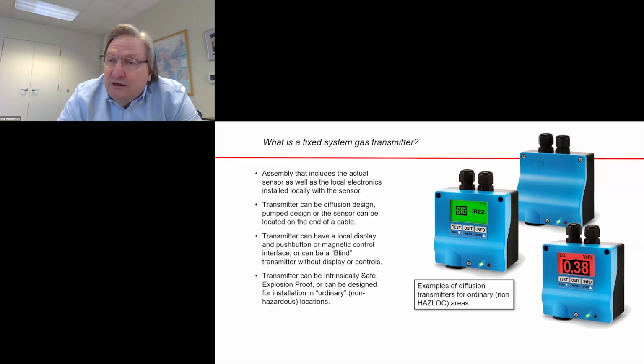That's one of the things that you define as you go through that selection process, those objectives in the AIHA white paper. Or you can have a transmitter that has a push button interface or a magnetic interface. Another part of the decision tree is knowing the hazards associated generally with what's going on in the area. If it is an area which is characterized by the potential presence of combustible gas, then it is a hazardous location and it requires a product that is certified for installation in an area of that level of hazard.